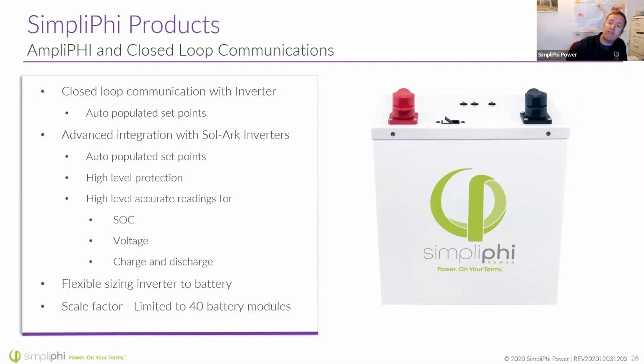And this breaker is a great feature because essentially you can turn the battery off, and it helps with troubleshooting if we need to start isolating batteries to take readings. It also helps with install because I can turn this battery off, knowing I'm not going to have a risk of shorting these terminals out. Of course, I still want to be using insulated tools to connect all this stuff up, but it's a great installation feature.